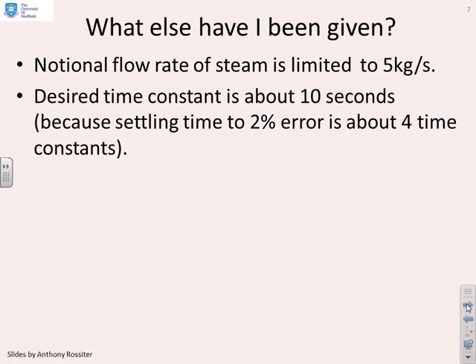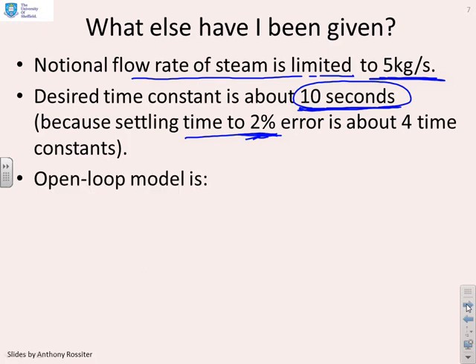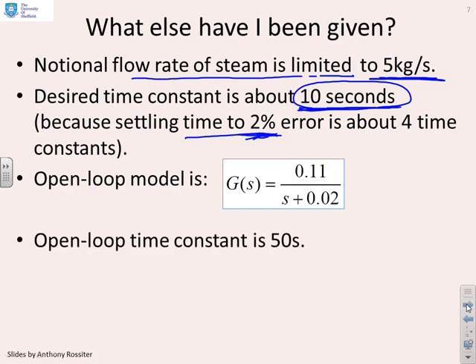What else have I been given? We've been told that the notional flow rate of steam is limited to five kilograms per second. The time constant we would like for this process is 10 seconds - we were told 40 seconds is how long you're allowed to get to within two percent, that means four time constants, therefore the actual time constant you want is about 10 seconds. We've derived the open loop model: 0.11/(s+0.02) between steam flow and temperature change. From this we can see the open loop time constant is 50 seconds, because 50 is the inverse of 0.02.